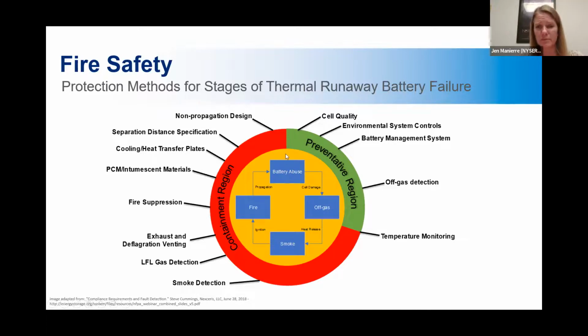So between the battery being abused at the top and then overheating and off gassing over at like the 3 o'clock mark, what we're looking at is the green region, the preventative region, where you can stop the thermal runaway from happening, nip it in the bud, if you will. And some of the ways we do that is, of course, starting at the top with cell quality. Throughout the fire code, there are different UL standards that the battery cells and the systems themselves also need to meet. So cell quality, obviously the best place to start. If you have good batteries, they're less likely to go bad. Fairly obvious.